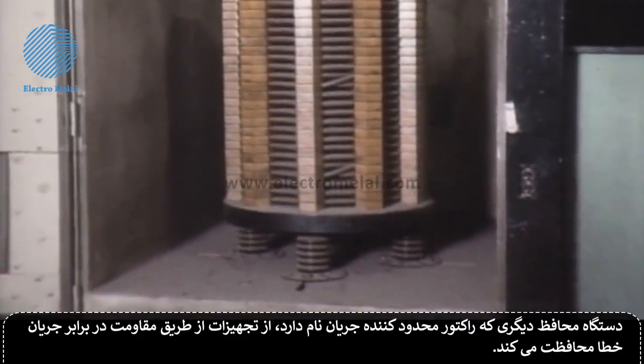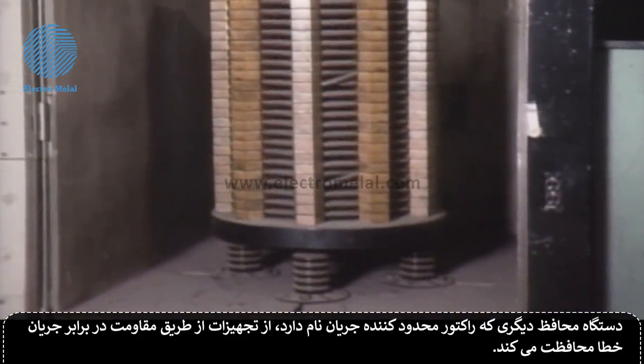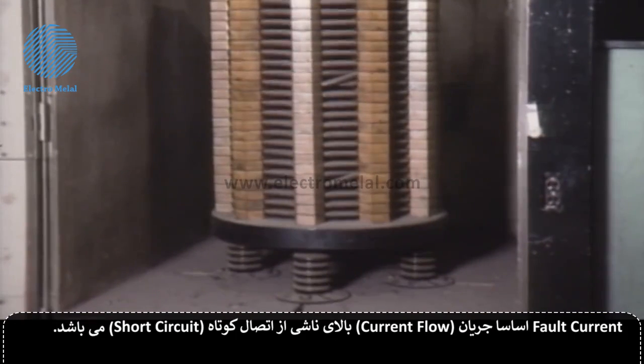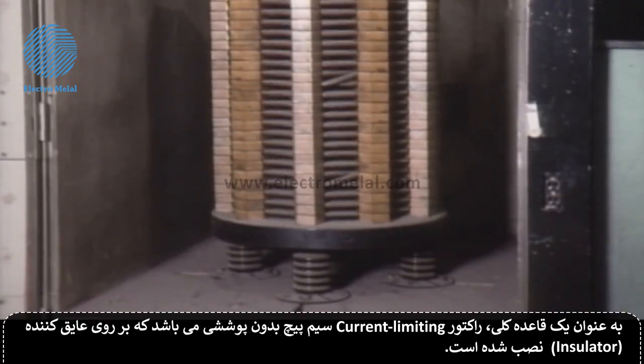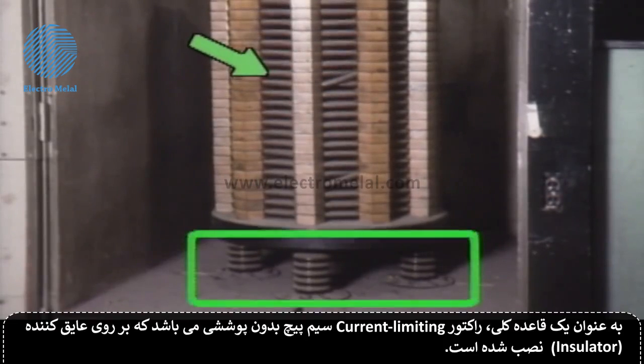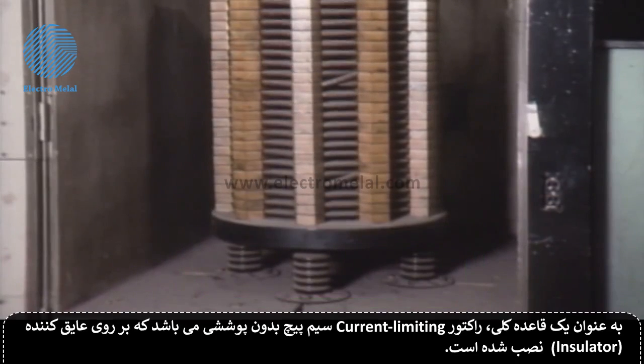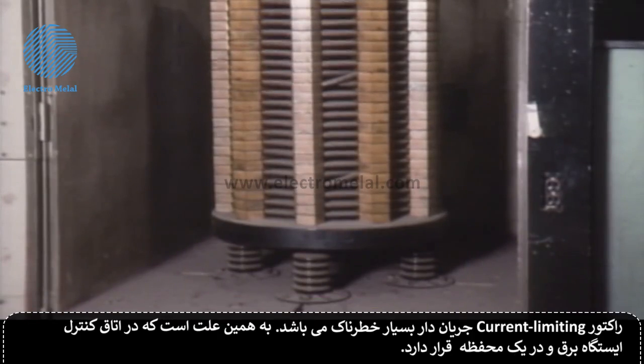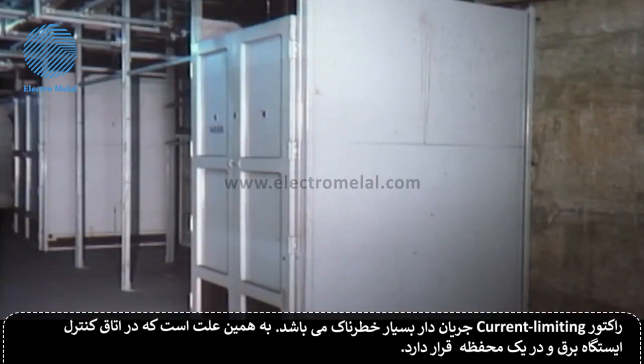Another protective device, called a current limiting reactor, protects system equipment by resisting the flow of fault current. Fault current is basically high current flow caused by a short circuit. As a general rule, a current limiting reactor is an exposed coil of wire mounted on insulators. An energized current limiting reactor is very hazardous. That's why they're usually housed inside a substation control house in a protective enclosure.